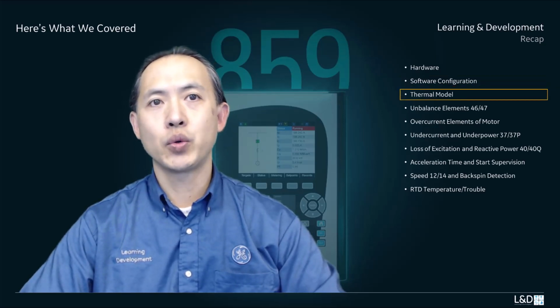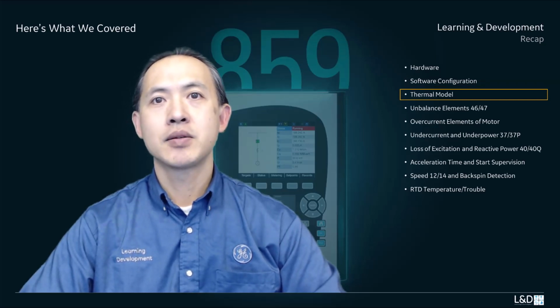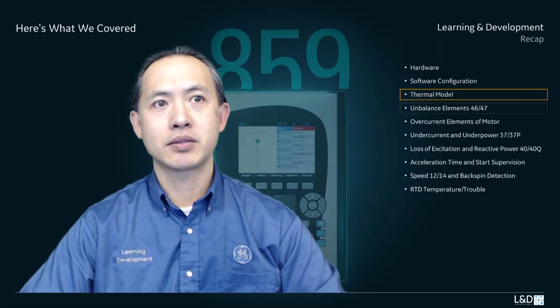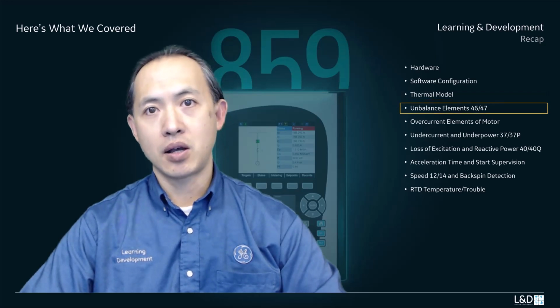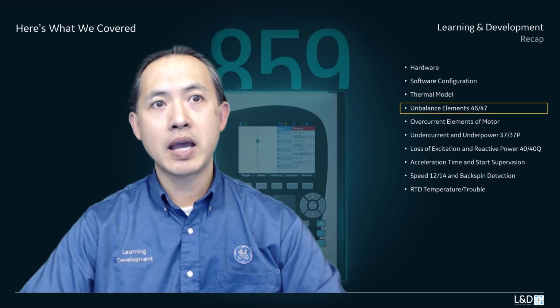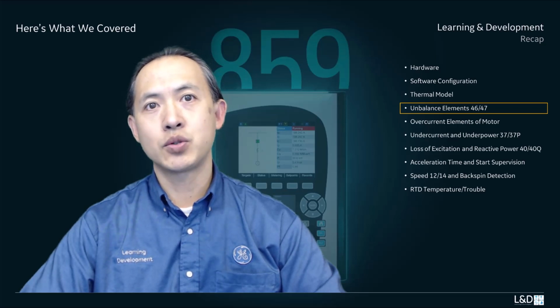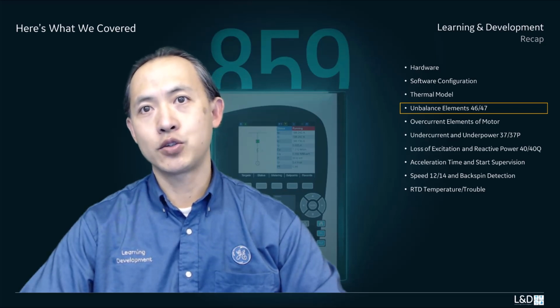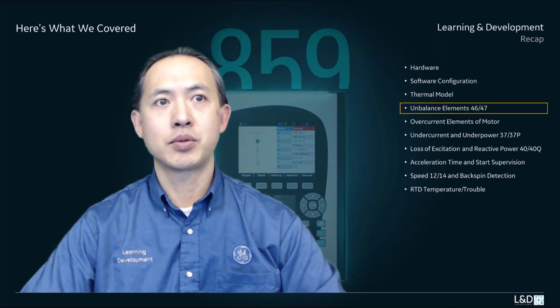In the thermal model, we introduced thermal model theories like unbalance bias and RTD bias. Then in the unbalance elements 46 and 47, we introduced the current unbalance calculations and phase reversal protection.